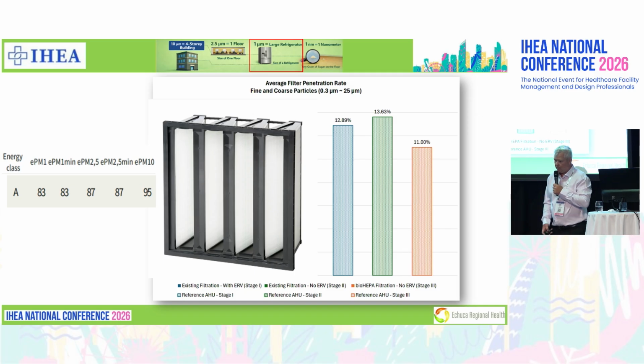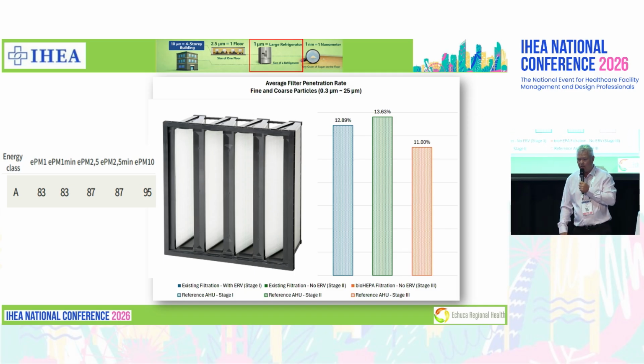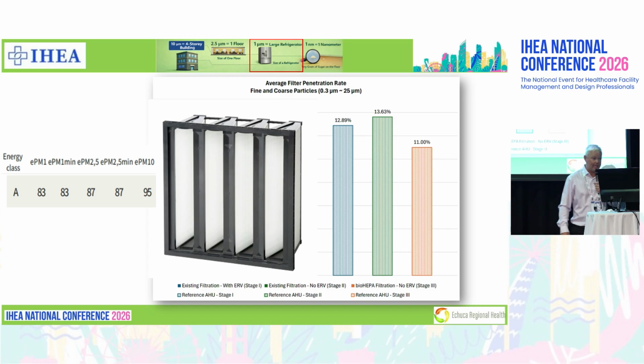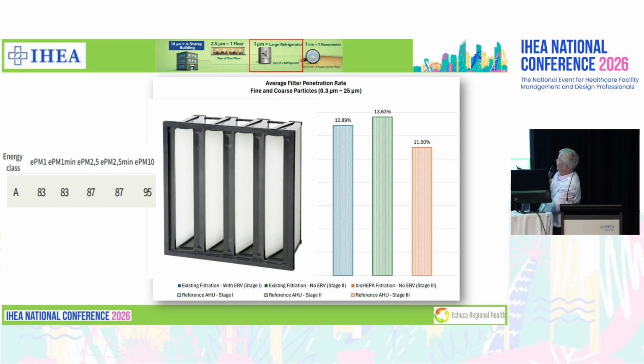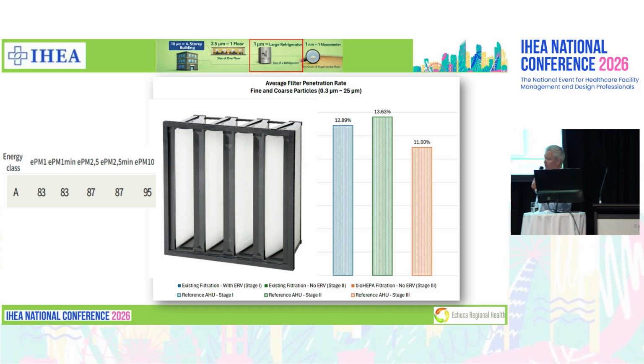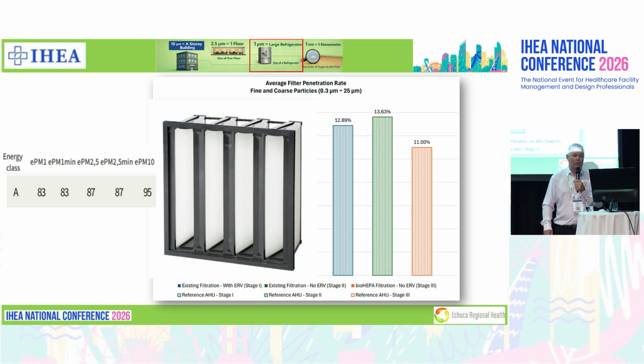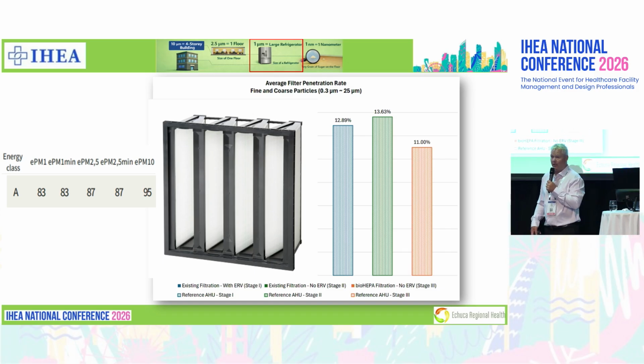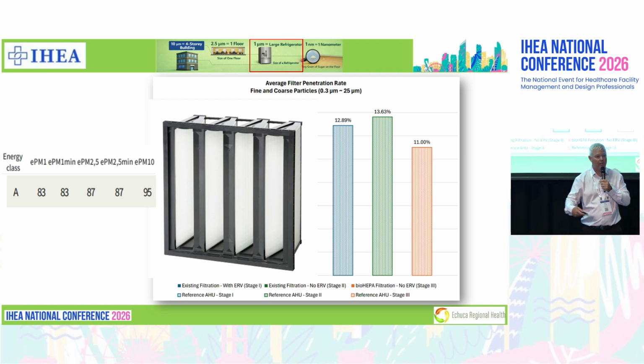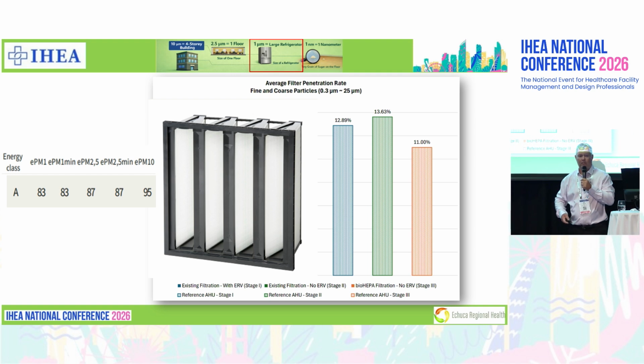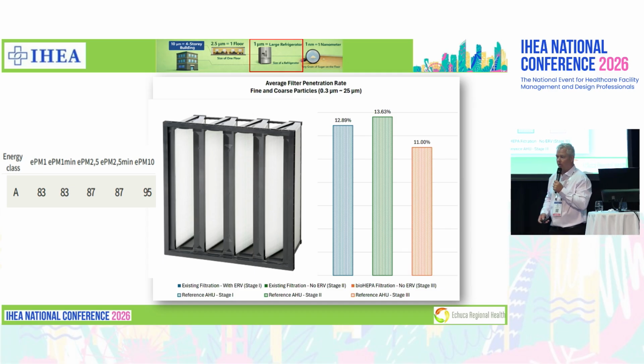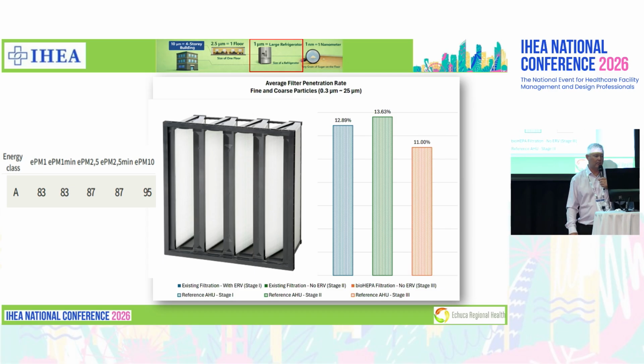You can see that the average filter penetration rate for particles 0.3 to 25 microns, left of the red box at the top - remembering our efficiency should be for this filter somewhere around 83% - amazingly, we had about 13.6% penetration. So this filter is performing almost exactly as designed in situ in our facility, which is pretty amazing because you put filters in and you just sort of expect they work. But this actually allowed us to understand that we were right on the money.